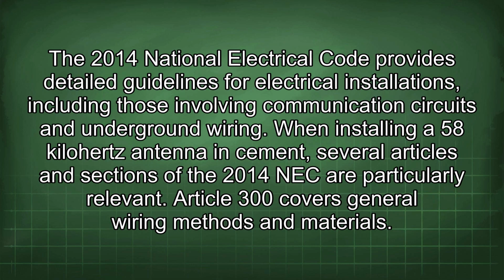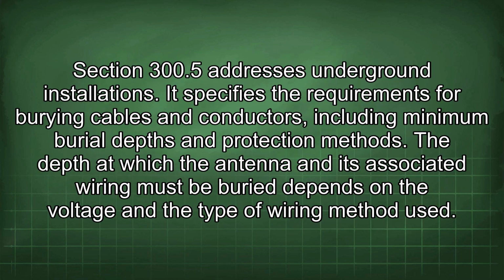The 2014 National Electrical Code provides detailed guidelines for electrical installations, including those involving communication circuits and underground wiring. When installing a 58 kHz antenna in cement, several articles and sections of the 2014 NEC are particularly relevant. Article 300 covers general wiring methods and materials. Section 300.5 addresses underground installations. It specifies the requirements for burying cables and conductors, including minimum burial depths and protection methods.